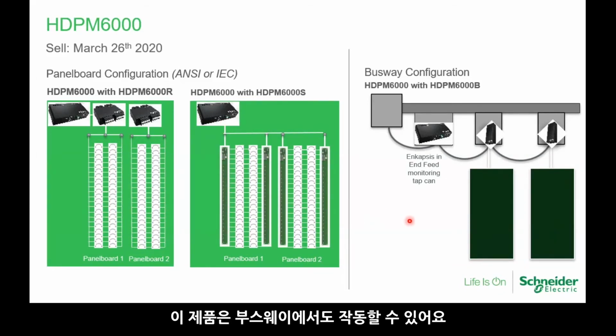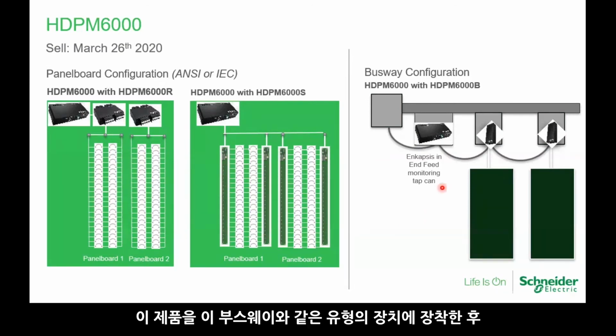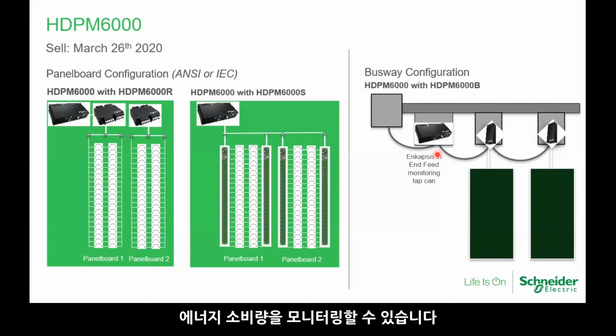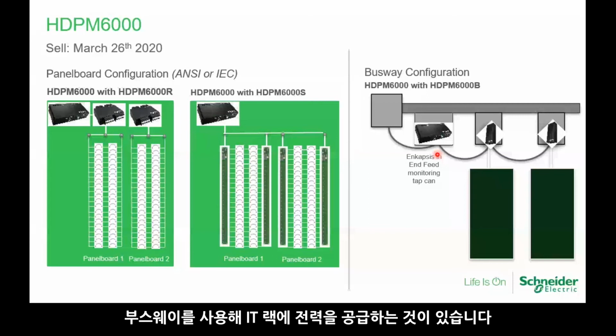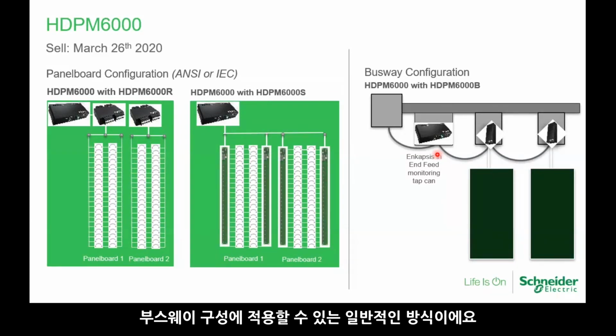But of course, this offer can also work on the busway. If you are familiar with busway, we can mount this offer on the tap-off units of the busway and then link back to the system or to a BMS, where you can monitor energy consumption of individual IT racks. So there are two ways you can see in the market for data centers: one is using the PDU concept, the other is using busway to power up the IT racks. This is a typical way we can apply it in busway configurations.